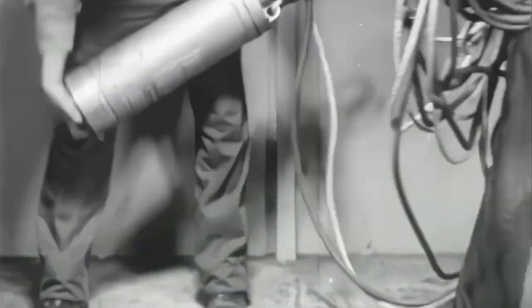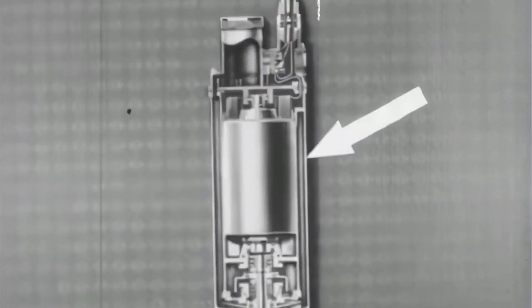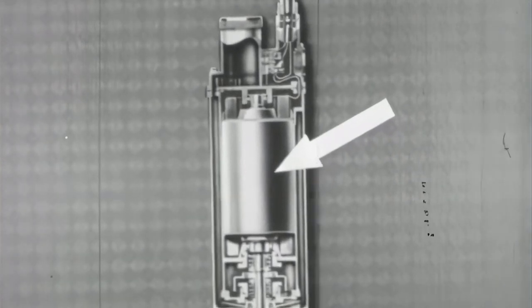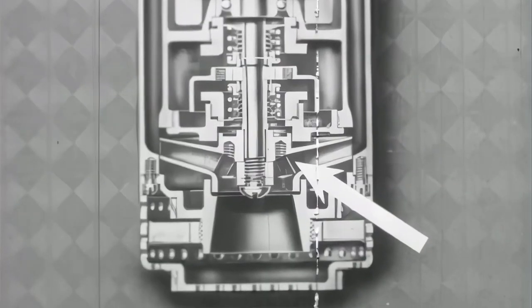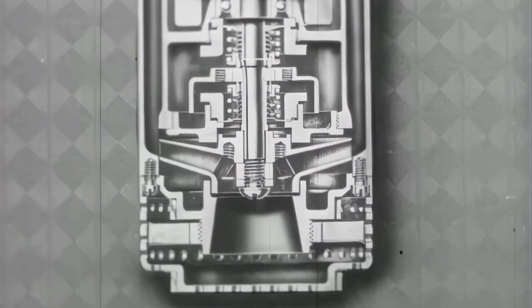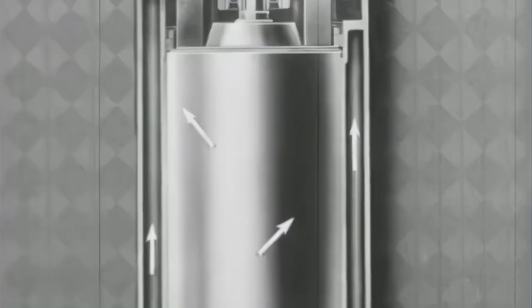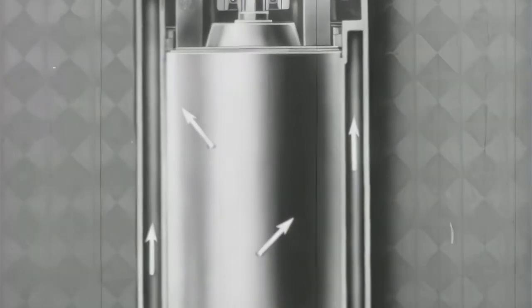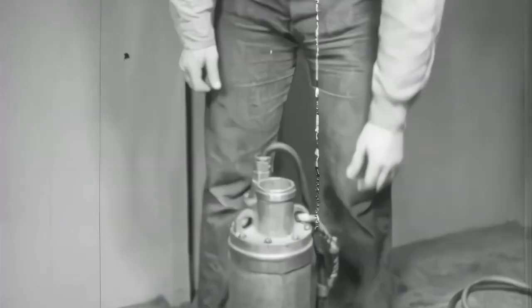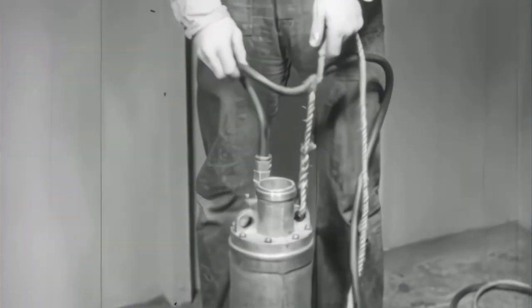The portable electric submersible pump can be handled by one or two men. This pump consists of a solid brass case enclosing an electric motor of either 220 or 440 volt AC or DC rating, a rotating impeller, a strainer, and seals which keep the water out of the motor. Water enters the intake, passes through the impeller, circulates around the motor housing to cool it, and is discharged through a two-and-a-half-inch hose connection at the top. A lowering line is always used on the pump so that no strain will be put on the power cable; plenty of slack is allowed.